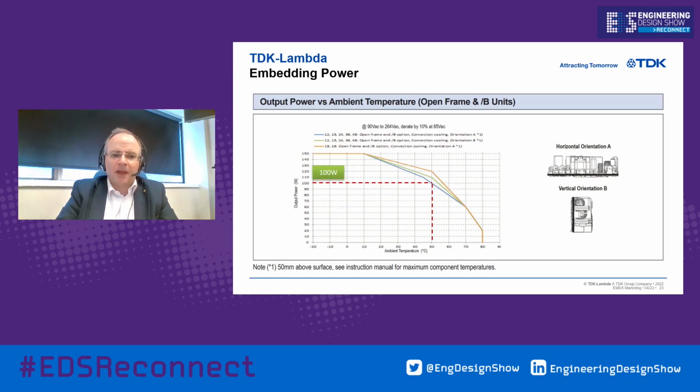As we have seen, adding a U-channel with a top cover can improve the EMI and reduce the risk of accidental shock. However, you also have to consider the possibility of derating the output power. This is because the metal shield can restrict the natural airflow. Therefore, you will need to refer to the manufacturer's derating curves. I've given an example taken from the CUS150M datasheet.